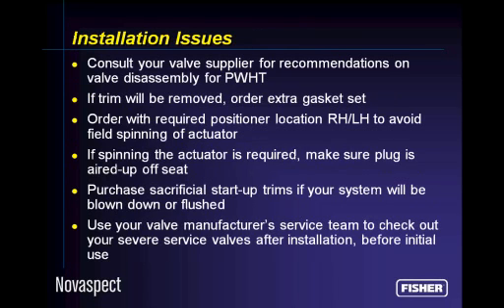If all else fails, consult your valve supplier for recommendations regarding valve disassembly prior to post-weld heat treatment. If we tell you that the trim has got to be taken out before you do that, well, let's make sure that we order an extra gasket set, so when you take it apart, we've got new gaskets to put it back together.